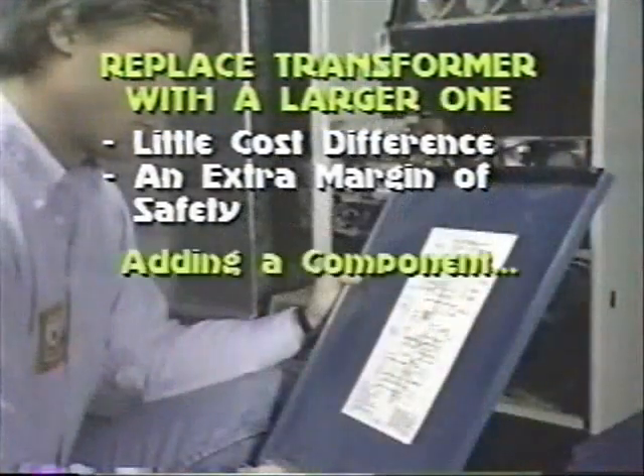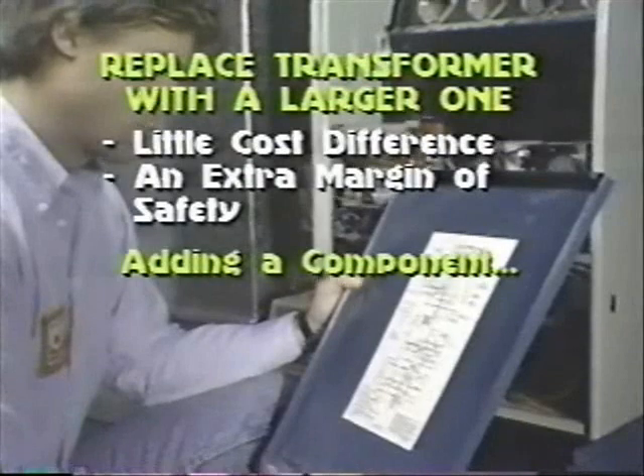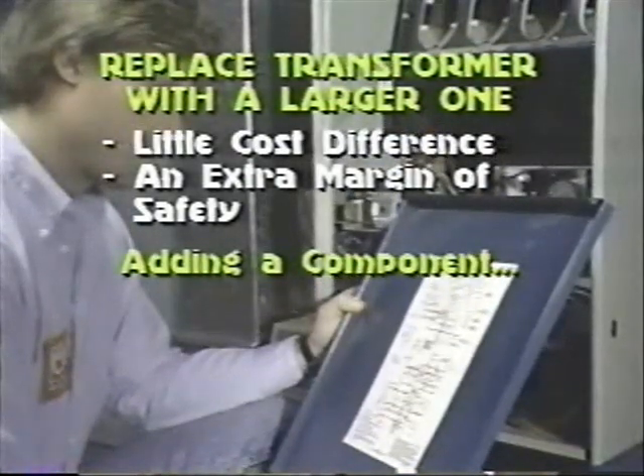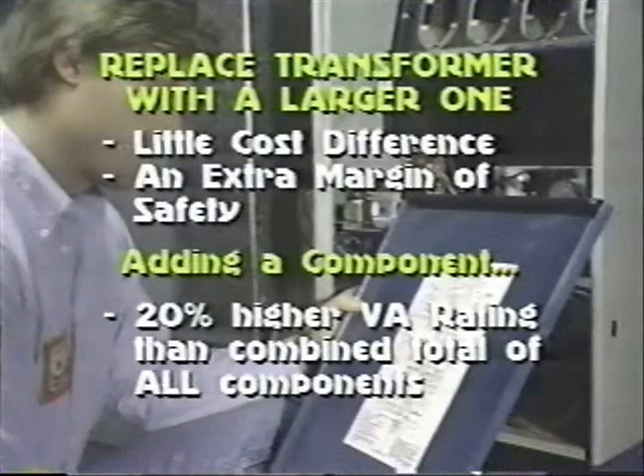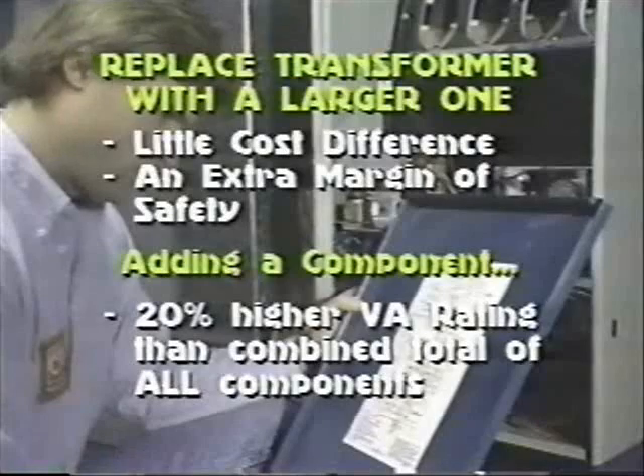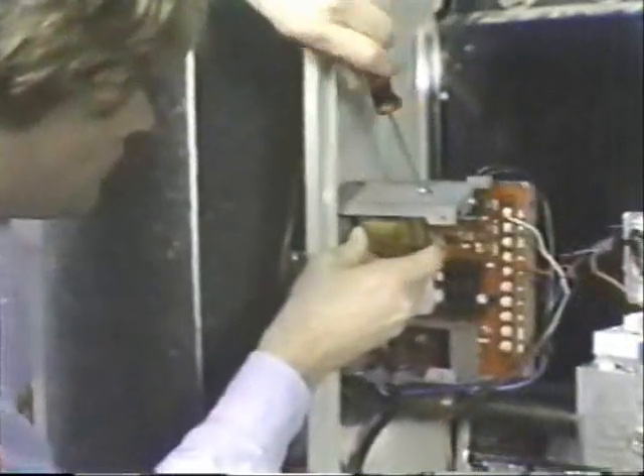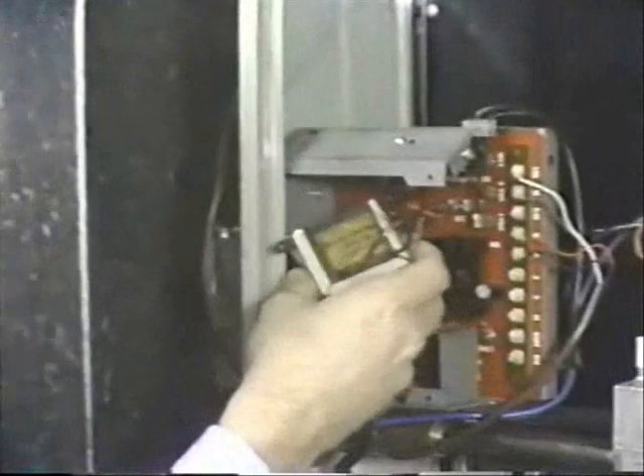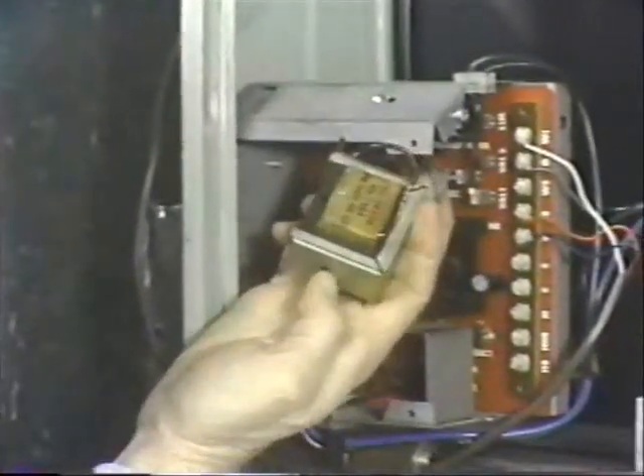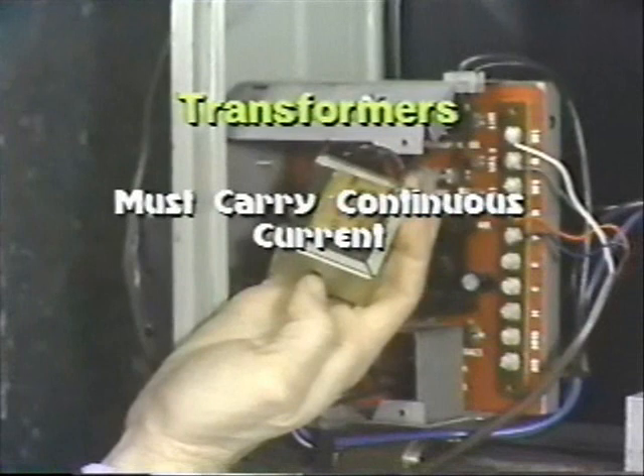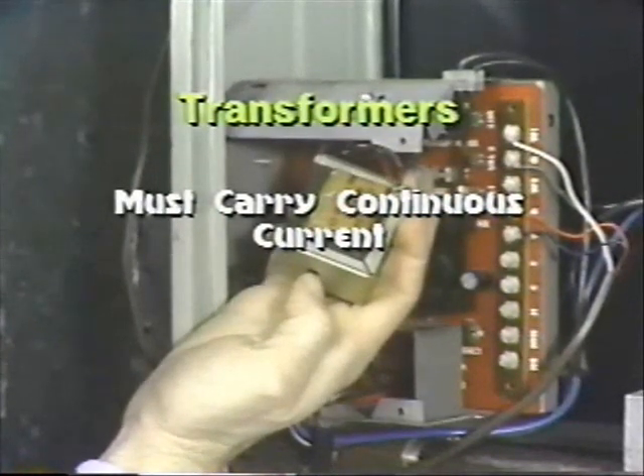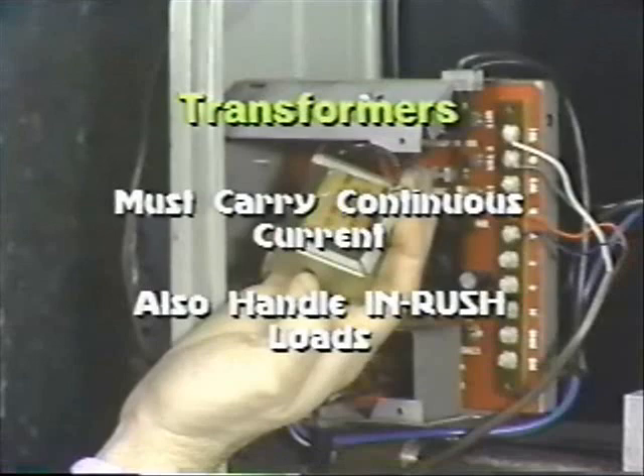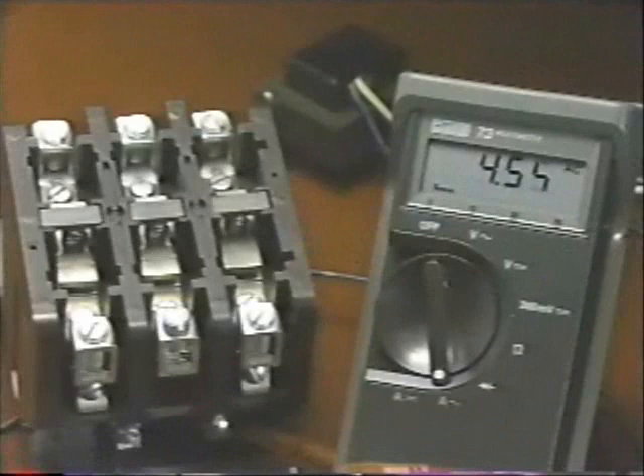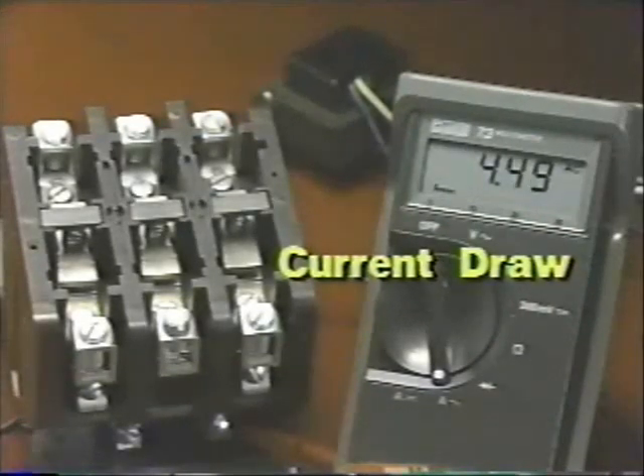When adding a component, such as a humidifier, check the manufacturer's recommendations. Generally, you want a transformer with a VA rating about 20% higher than the combined operating VA of all the components being controlled. Size, however, isn't the only consideration. Quality and performance are also important. Remember, not only must a transformer be able to carry the continuous current of a circuit's components without overheating, it must also be able to handle inrush or startup loads. It takes more current, for example, to pull in a contactor than it takes to hold it in.